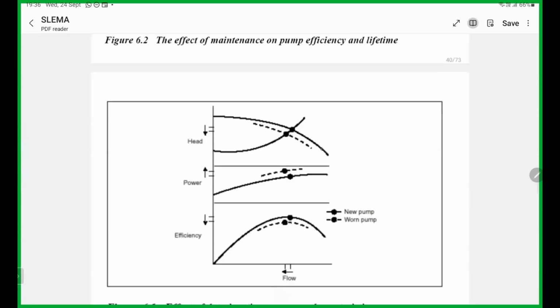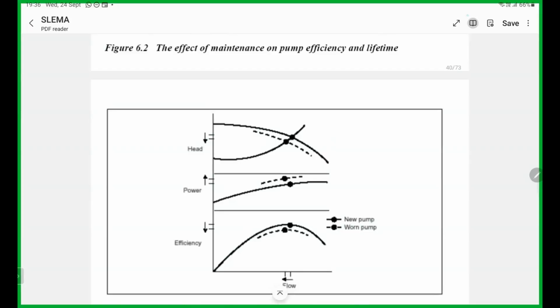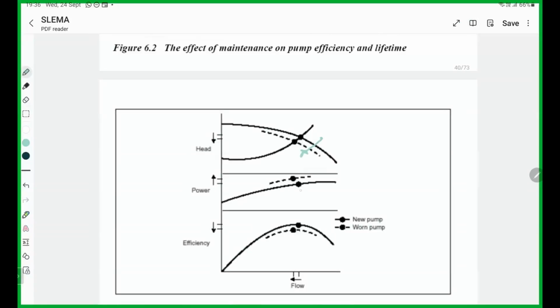Generally, pumps degrade. You have to keep that in mind. The pump curve shifts with age, the power requirement goes higher, and the efficiency goes lower. The important point is motor selection, because generally we buy a pump to use for more than about 10 years, and within these 10 years the efficiency goes down. So you have to select the motor at least 1.1 times greater than the power requirement at the duty point or total pump curve.